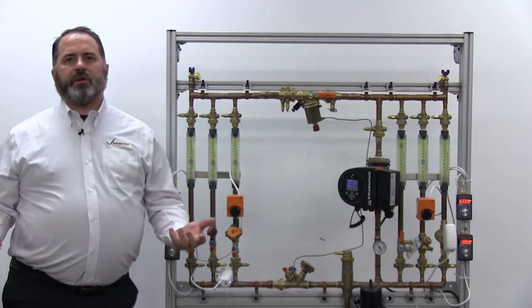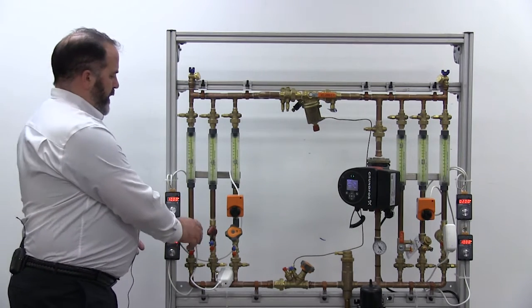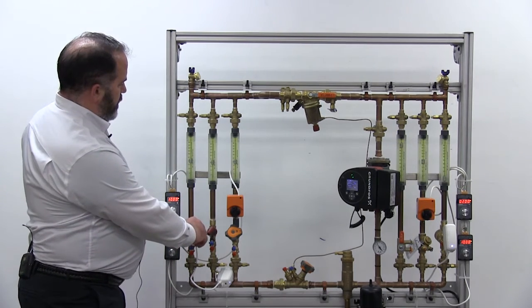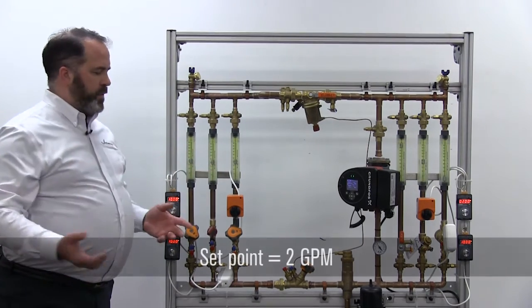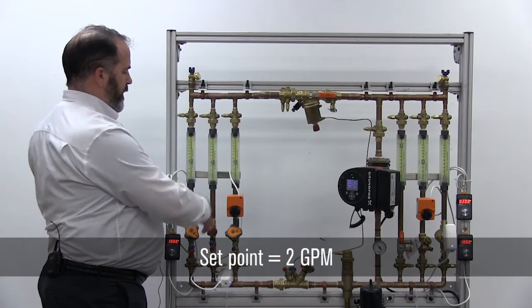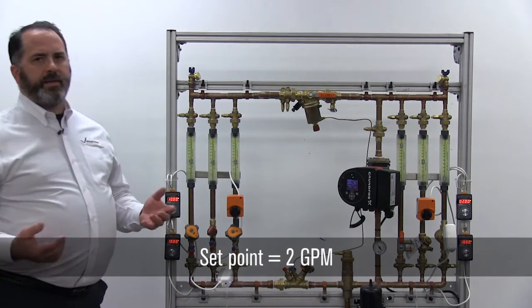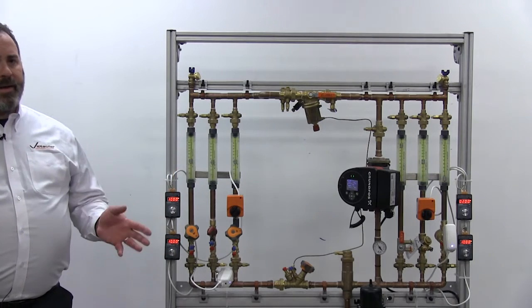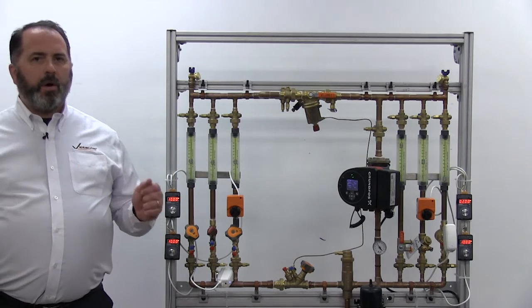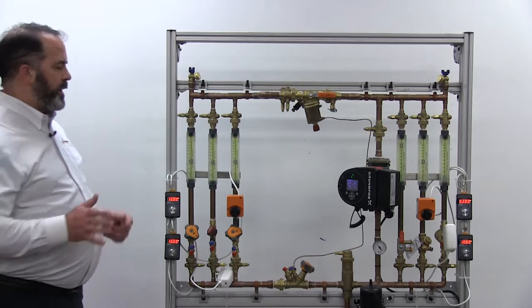We're going to start by what we call proportionally balancing the system, so we'll go to each of our coils. We'll go to the balancing valves, we'll set those valves so they're all equal. So we'll go across from one to two, starting from the index coil working our way into the system, and set all of our coils so they're all equal flow, not necessarily a design flow at this point, but all equal.